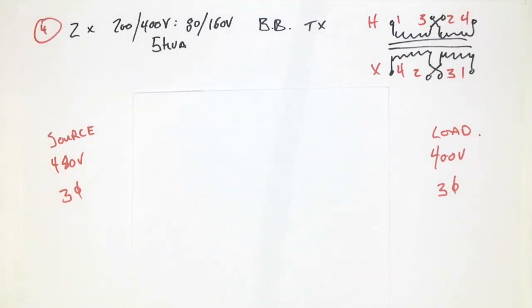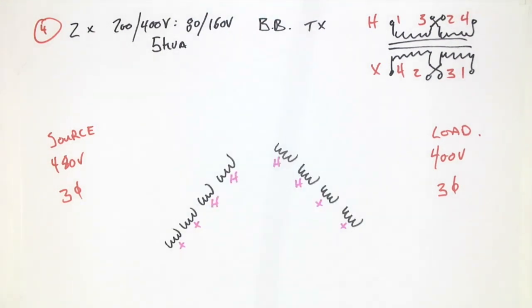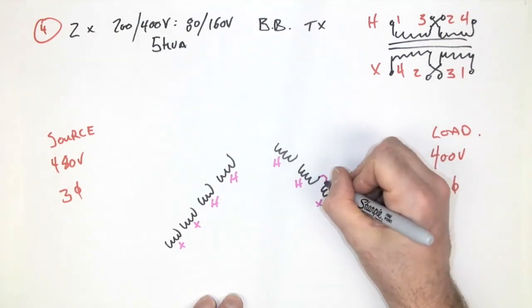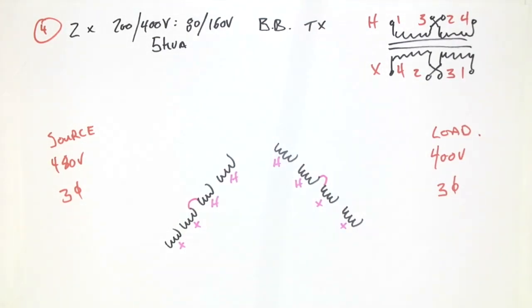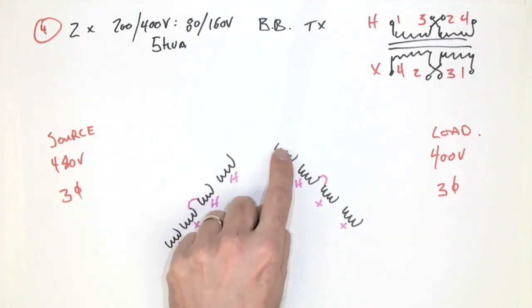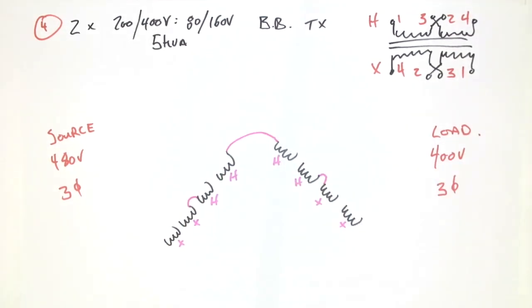We're going to connect this in open delta, which means there's a few assumptions that we can first bring to the table. First, I know I've got to have the X and the H winding connected together. And also, I know that I need to have this common connection up here to make my open delta sort of a pinnacle or pyramid point.